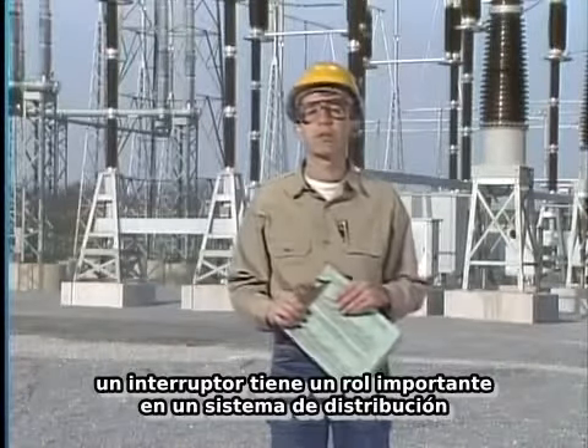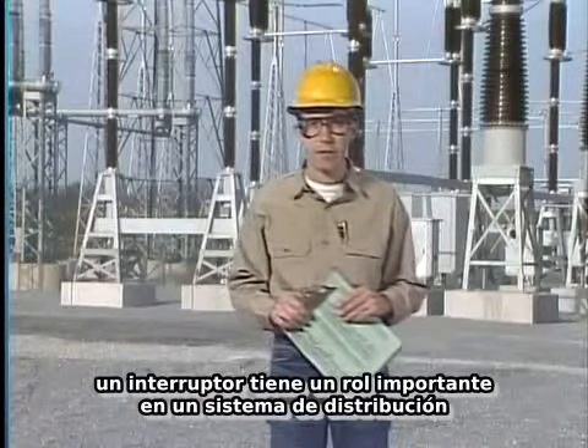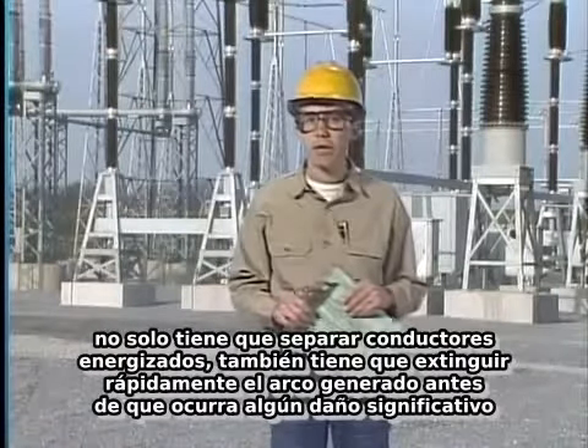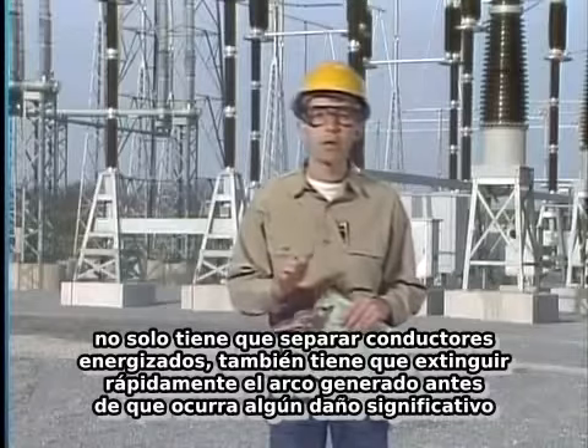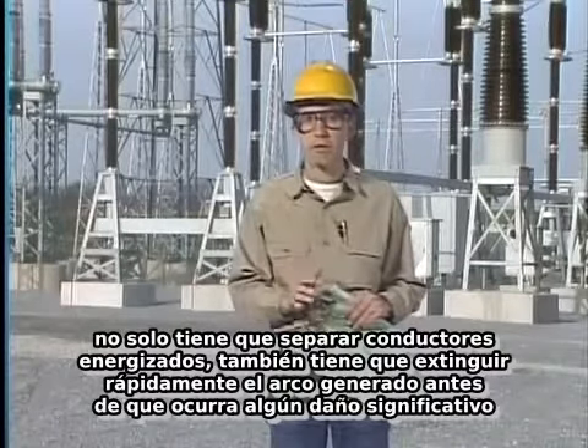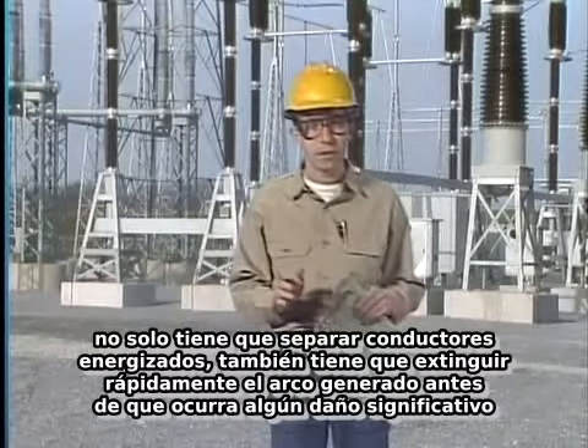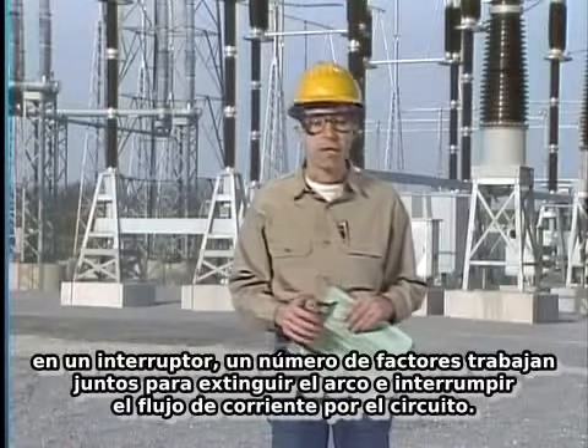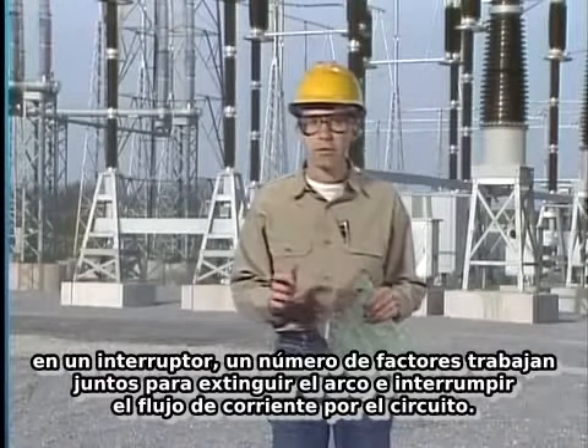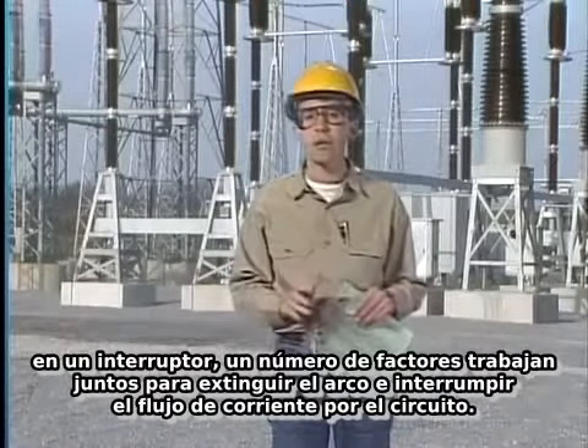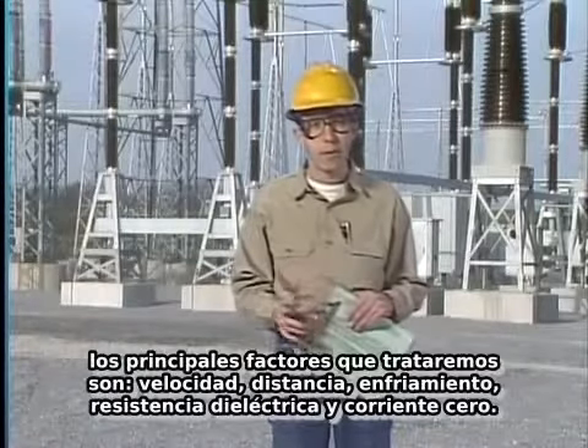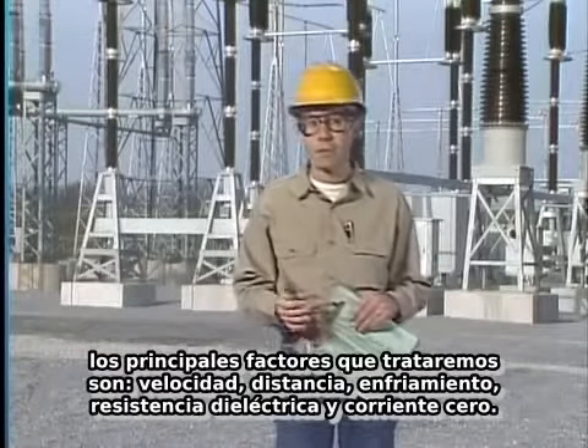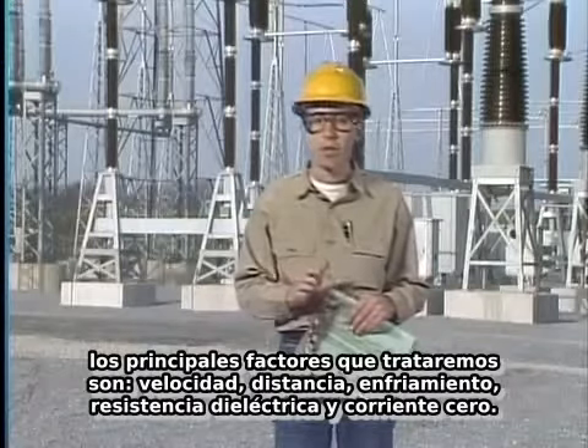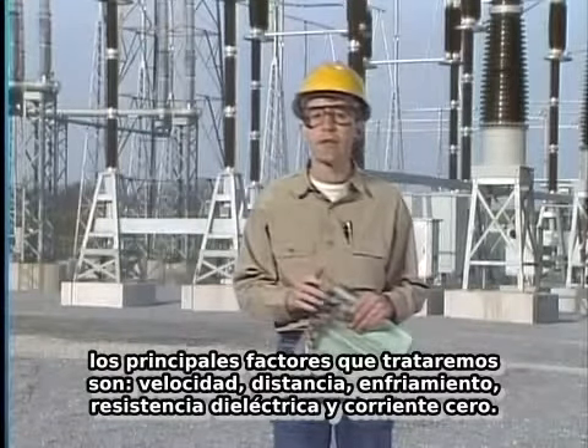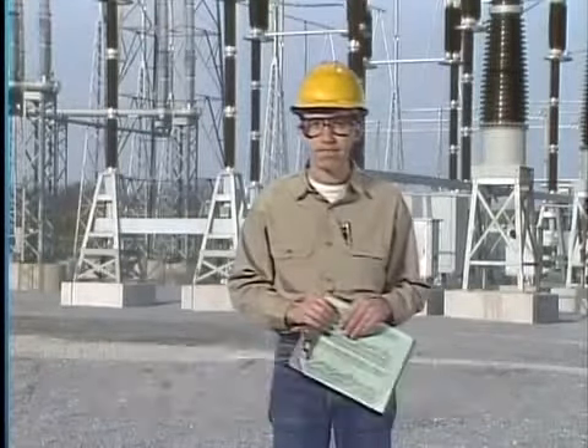A circuit breaker plays a critical role in a T&D system. It not only has to separate energized conductors, but it also has to quickly extinguish the arc that is created before any significant damage occurs. In a circuit breaker, a number of factors work together to extinguish an arc and interrupt a circuit. The main factors we're going to look at are speed, distance, cooling, dielectric strength, and current zero.